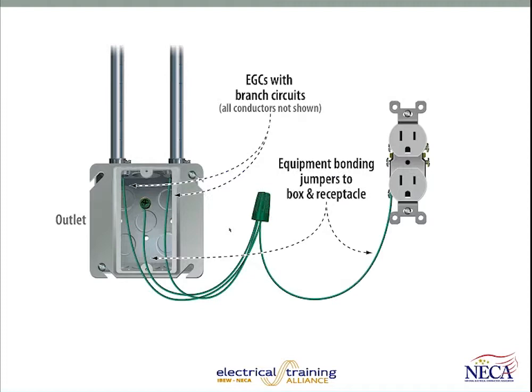So this clarifies that in the graphic it's very simple because there appears to be just one circuit. But if there are multiple circuits within the same box, the requirement now is to connect all the equipment grounding conductors together and to the box and associated device if it's required.